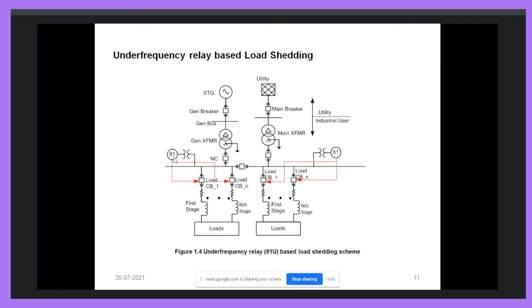But if the difference between load and generation is low, for that case also the frequency relay will disconnect the same amount of load which is required for the worst operating scenario, because the relay settings cannot be changed in real time. Once we have set the relay for a particular value and decided that much load will be disconnected for this frequency decrease, that will be fixed and will not change. So these schemes are not adaptive. They are fixed, and in these schemes the maximum load required to maintain stability is always disconnected from the system.